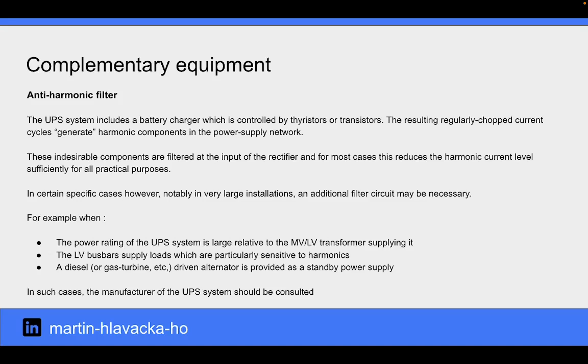For example, when the power rating of the UPS system is large relative to the MV-LV transformer supplying it, the LV busbar supplies loads that are particularly sensitive to harmonics, or a diesel-driven alternator is provided as a standby power supply. In such cases, the manufacturer of the UPS system should be consulted.